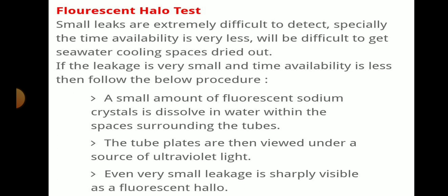Here, a small amount of fluorescent sodium crystal is dissolved in water in the space surrounding the tubes. The tube plates are then viewed under a source of ultraviolet light. Even a small leakage is sharply visible as a fluorescent halo.